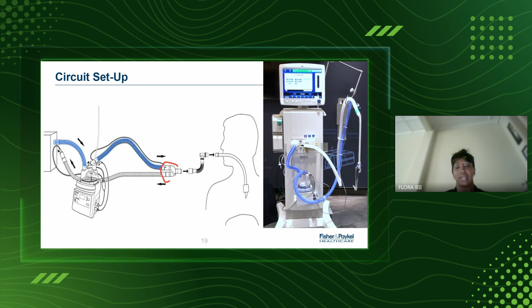For the reusable circuit range, these ones would basically comprise silicone circuits or circuits made of some material called Hytrel, and these ones are fully autoclavable. Now, fully autoclavable, meaning that you can use it for up to 60 times. You know, you can use it for more and more depending on the manufacturer's recommendations of the same.